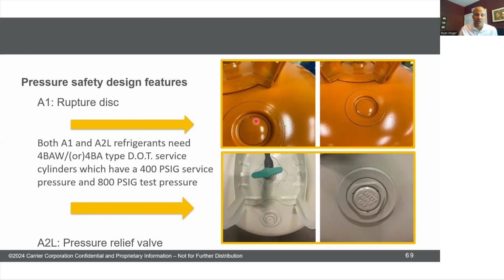So we've had those for years. Those are going away, and they're replaced with a relief valve. The difference being when the rupture disc blows, you lose the whole charge of the tank. When the relief valve opens, you just lose enough charge to get back down under the pressure limit. So you might have had a 20-pound cylinder, it got too hot, hence the pressure got too high. The relief valve opened up, it let some refrigerant out, and now you've got 17 pounds in the cylinder. Whereas in the old tank, you would have had zero. That's the only real difference. And I assume this is because they just want less refrigerant to leak out and possibly become an issue.